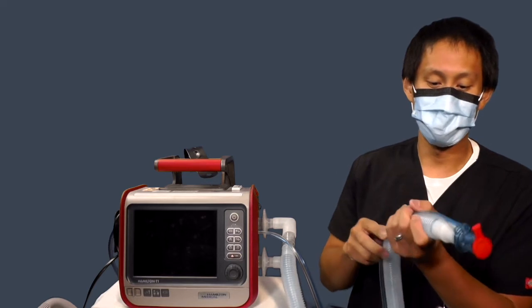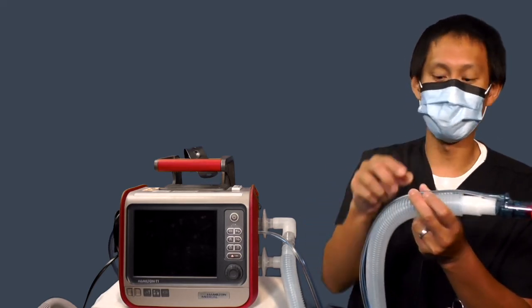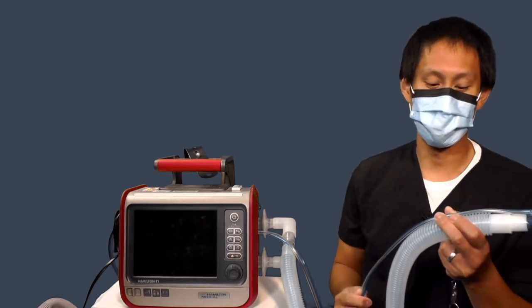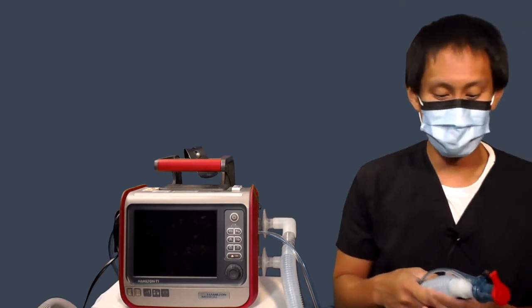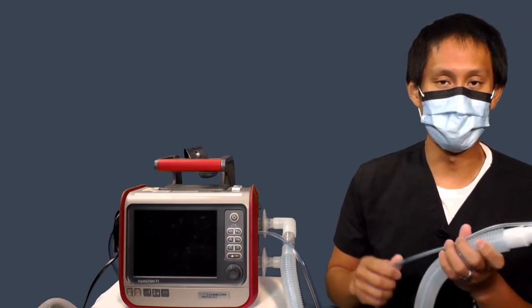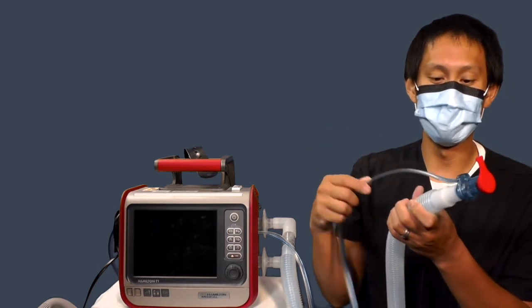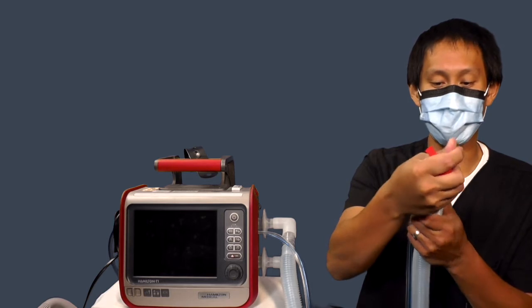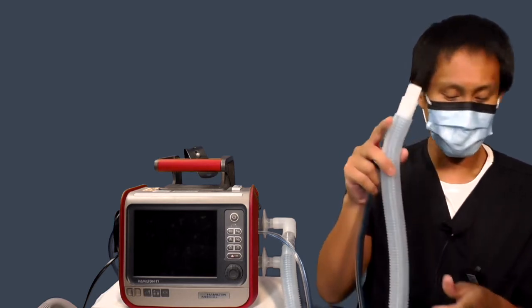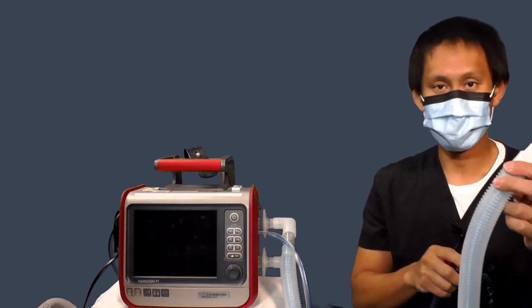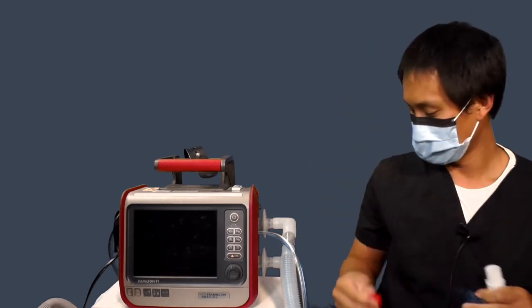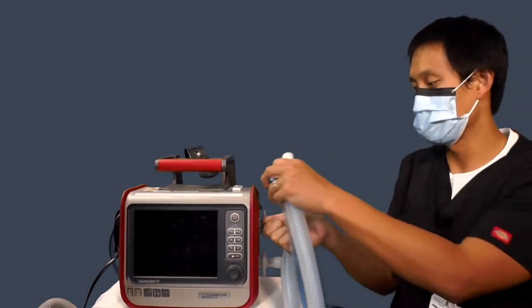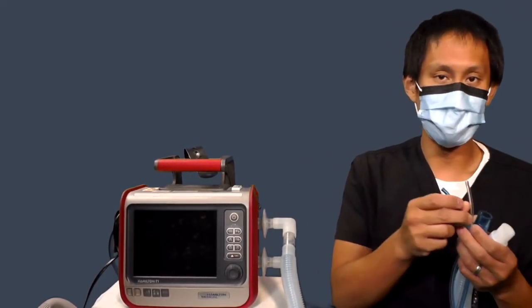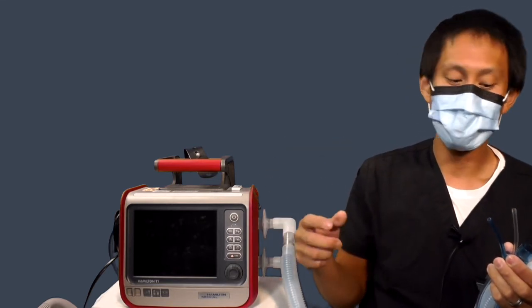It decreases your chances of getting micro bubbles inside your flow sensor tube. If by chance you do get condensation or water droplets inside your flow sensor tube, what you can do if you're ventilating a patient is disconnect the flow sensor from your circuit, hook this back up to your ET tube. So put the ventilator circuit back onto your ET tube, take the flow sensor out of line, disconnect the micro tubes from the side of the ventilator, and get a 10 cc syringe or something similar and stick it in the end of the microtubing.